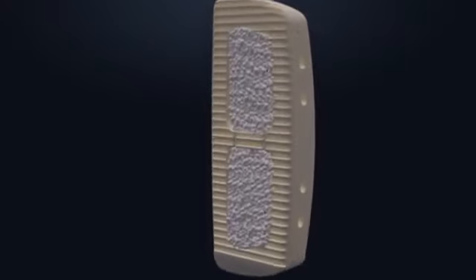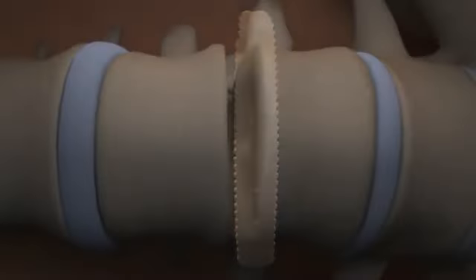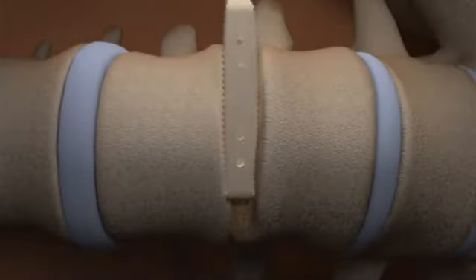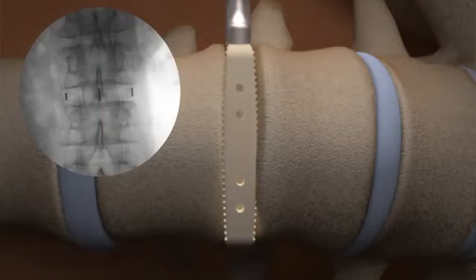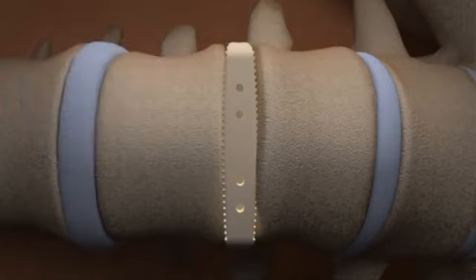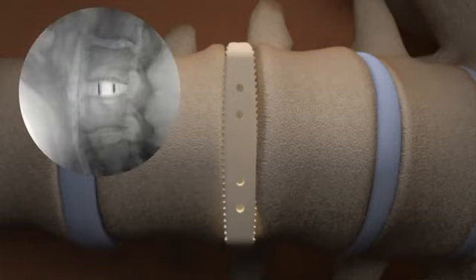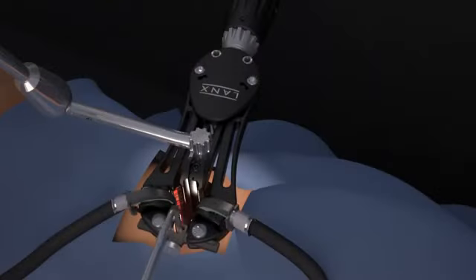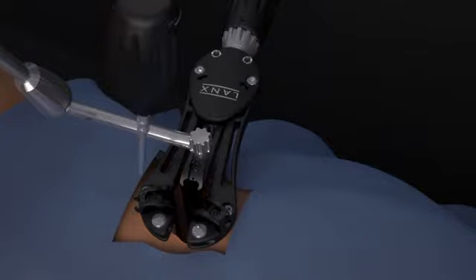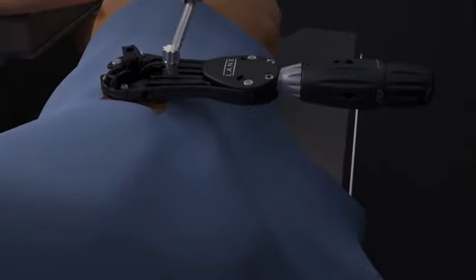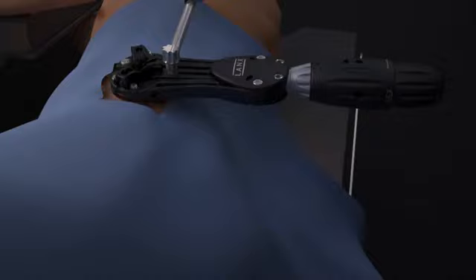Impact the implant into the disc space. Use AP fluoroscopy to confirm that the center implant marker aligns with the spinous process. The implant should span the width of the vertebral body. Remove the implant inserter and confirm the implant is in a good AP position using lateral fluoroscopy. Retract the posterior shim from the disc space. Return the retractor to the closed position. Disconnect the articulating arm from the retractor.